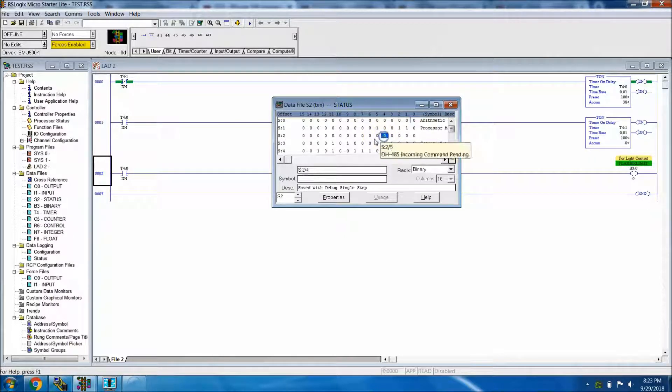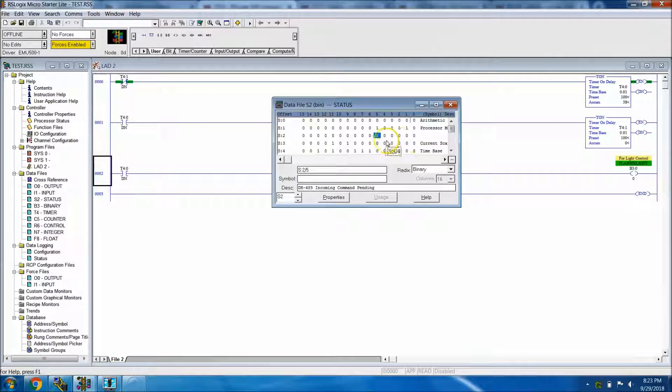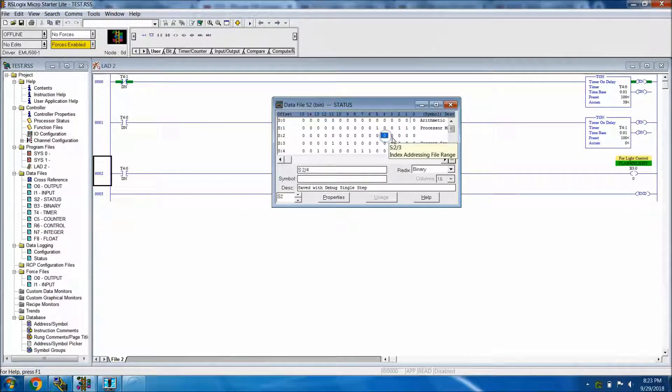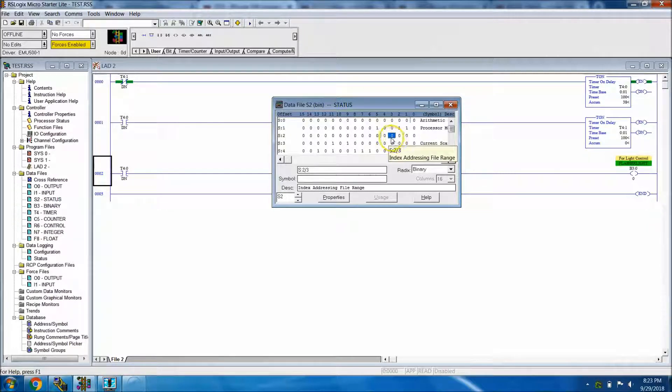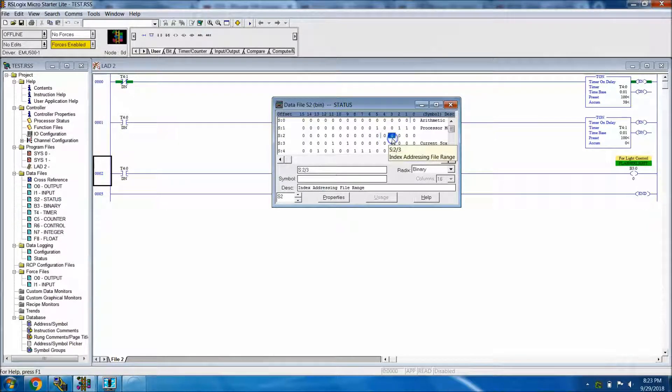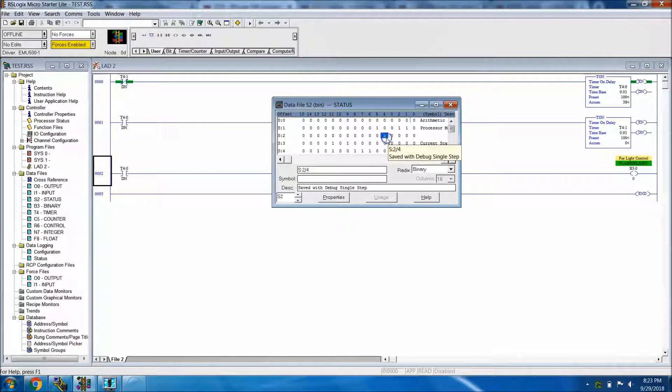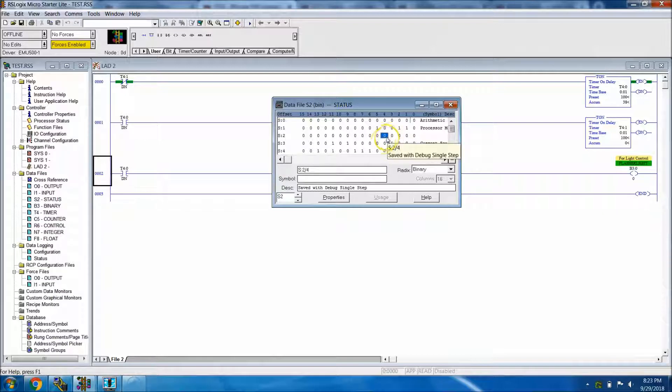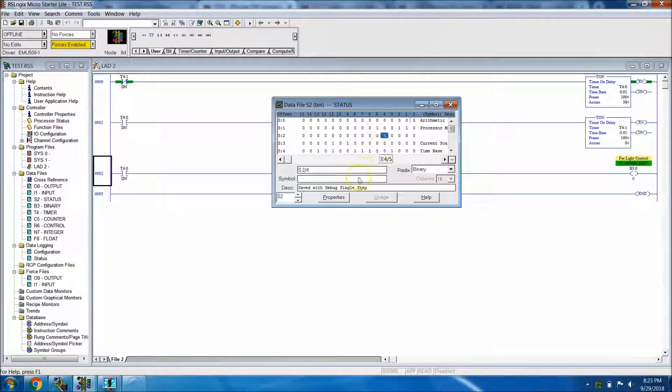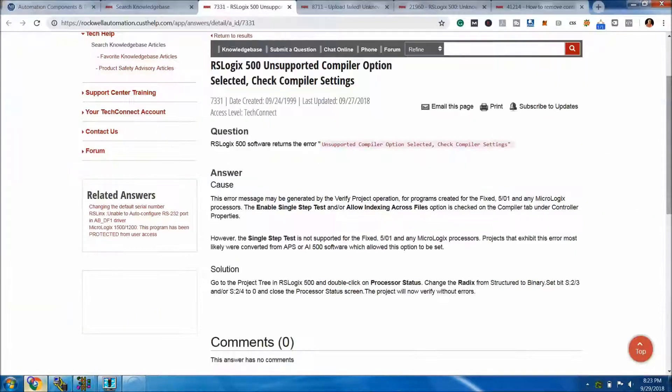Then they're telling you to look for this bit right here and this bit right here. It could change depending upon which bit you're actually using. I think it's S:2/3 and S:2/4, the two bits. If one of these is set high, you need to change that to zero, then that should solve the problem.